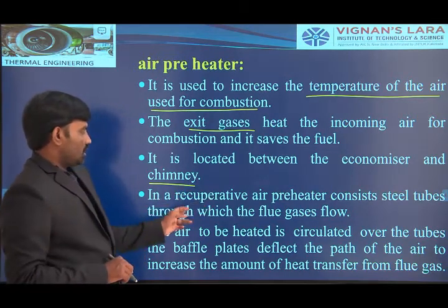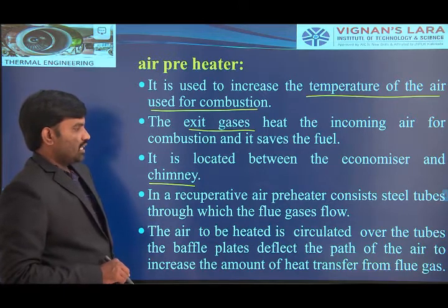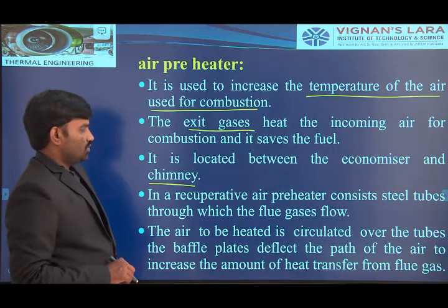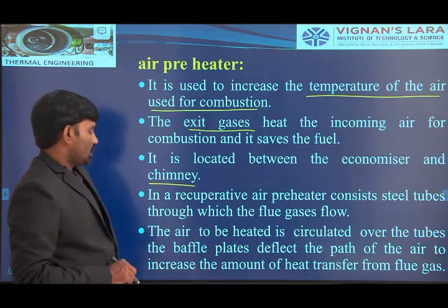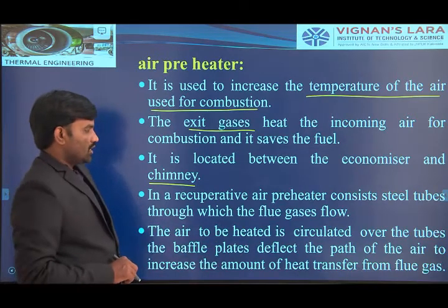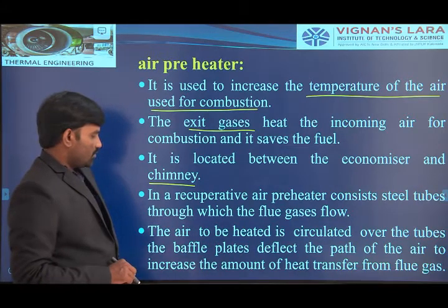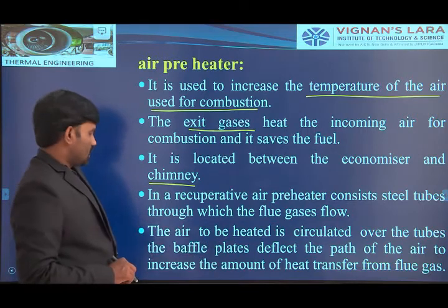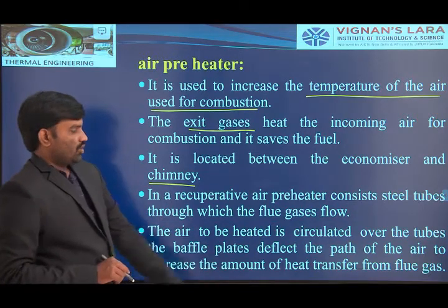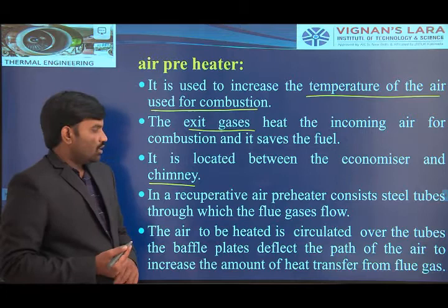A recuperative air preheater consists of steel tubes through which flue gases flow. The air to be heated is circulated over the tubes. The baffle plates deflect the path of the air to increase the amount of heat transfer from the flue gases.